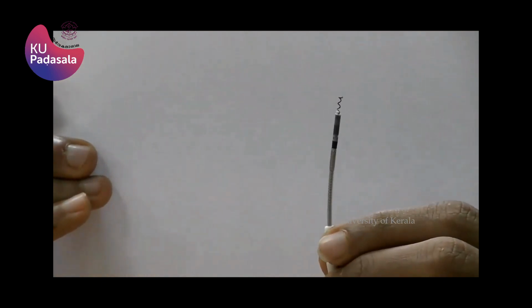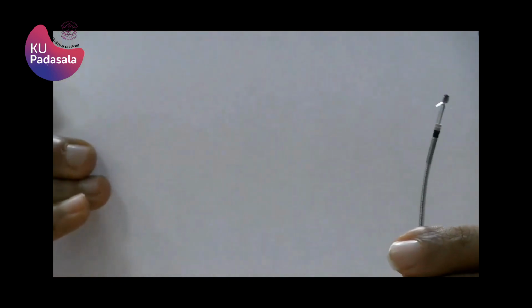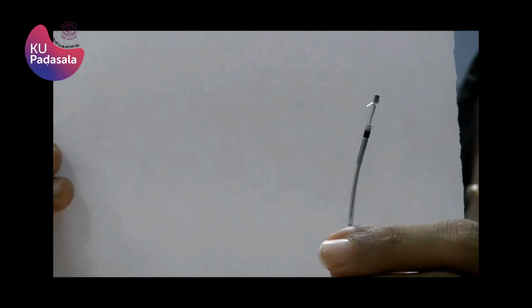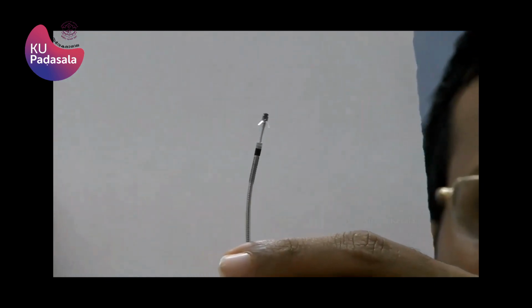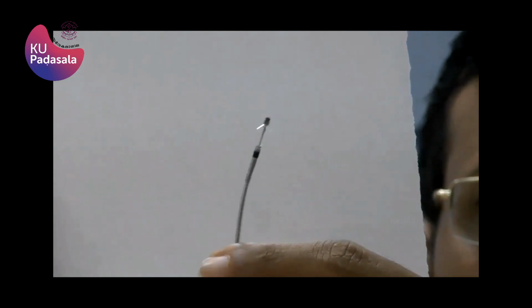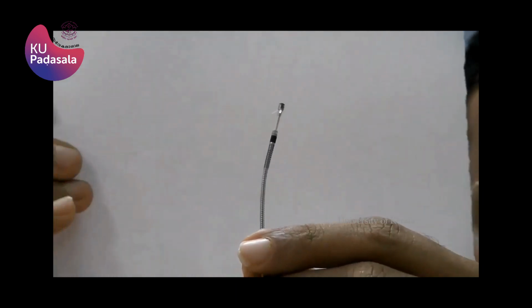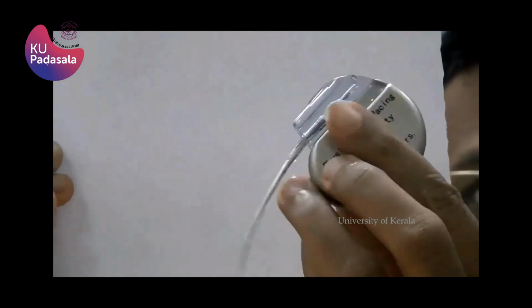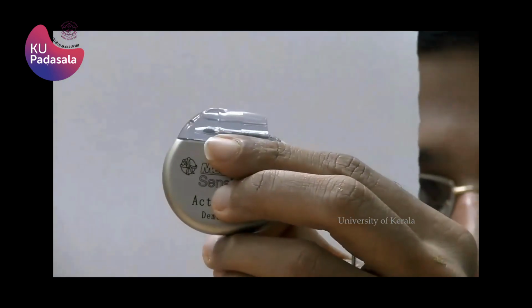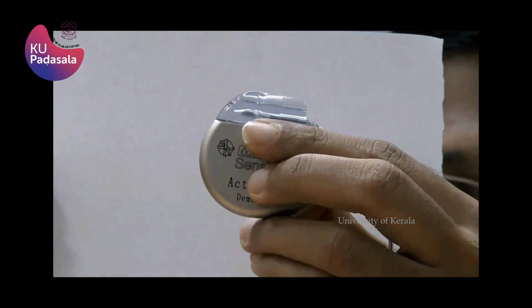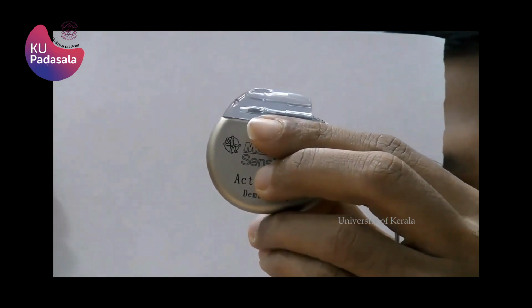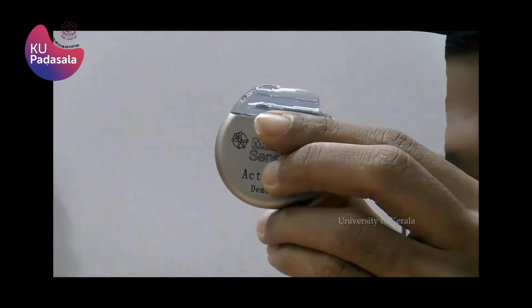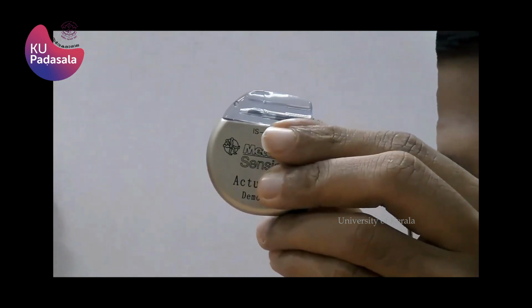So this is a screw-in lead. The screw is screwed into the heart muscle. This, on the contrary, is a tine lead where you can see there are small projections at the end of the lead, which is called a tine. And this tine is pushed into the heart muscle. And we generally don't prefer to use tine leads because they are difficult to extract if the patient needs an extraction later in life. And this is how a pacemaker looks. This pacemaker battery is inserted into the person below the skin in the pectoral region, which is just below the collarbone, otherwise known as the clavicle.